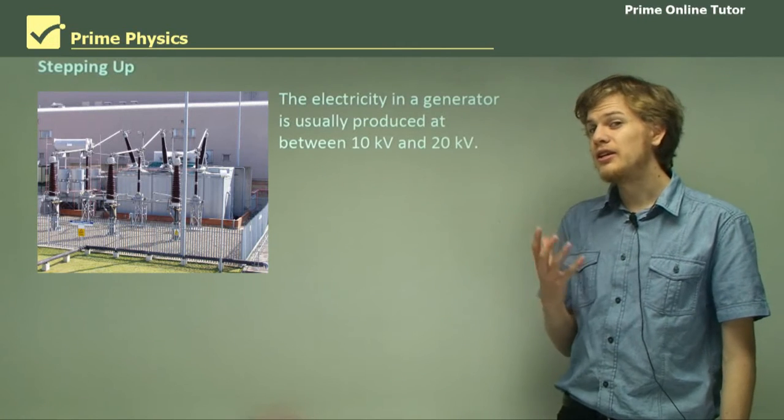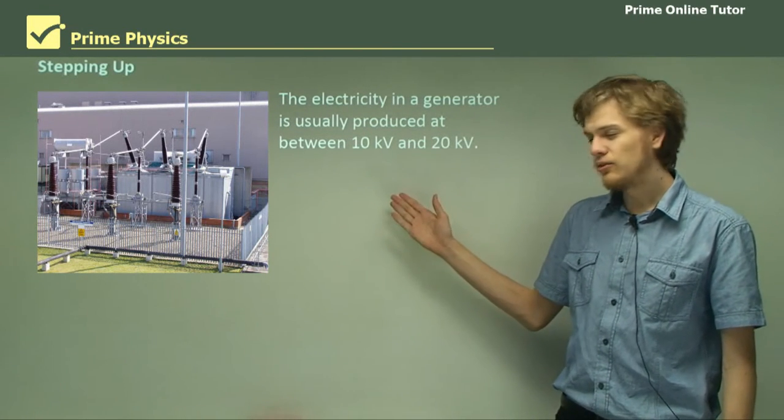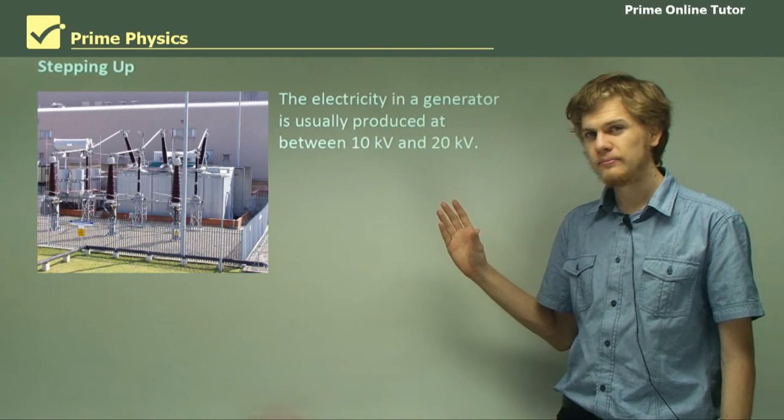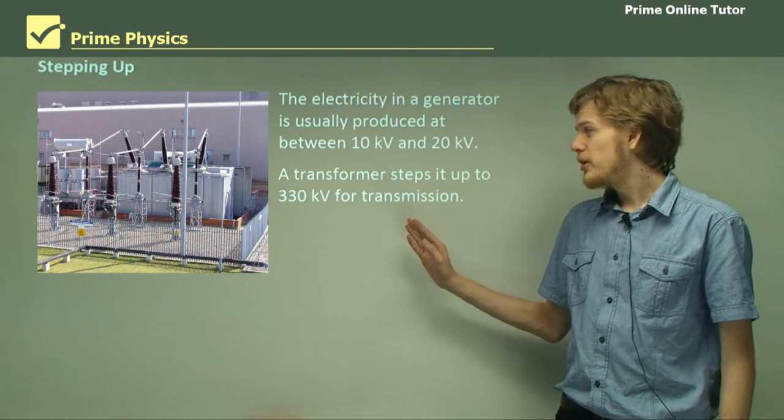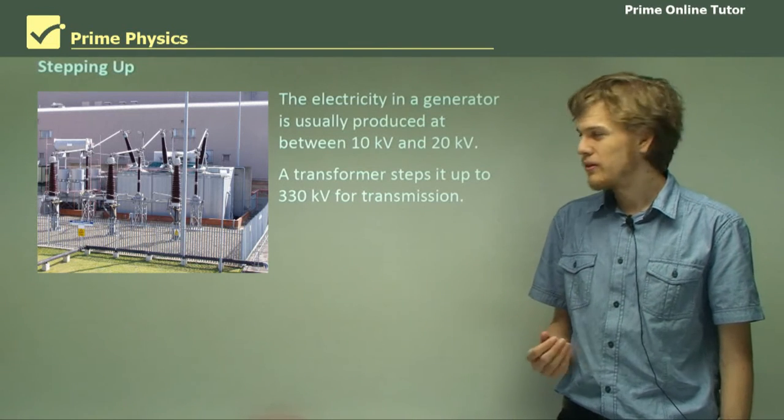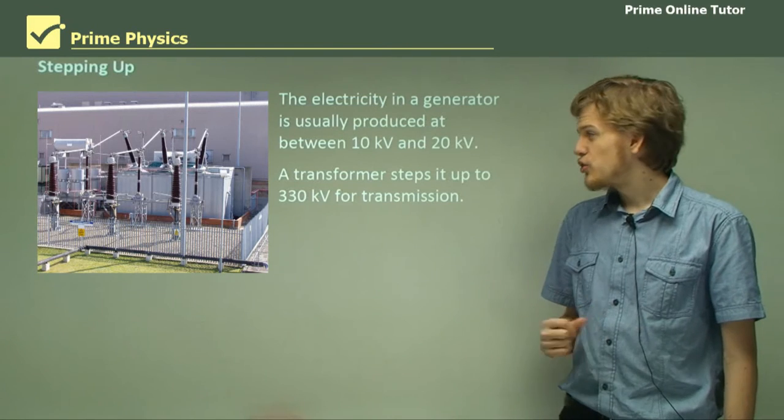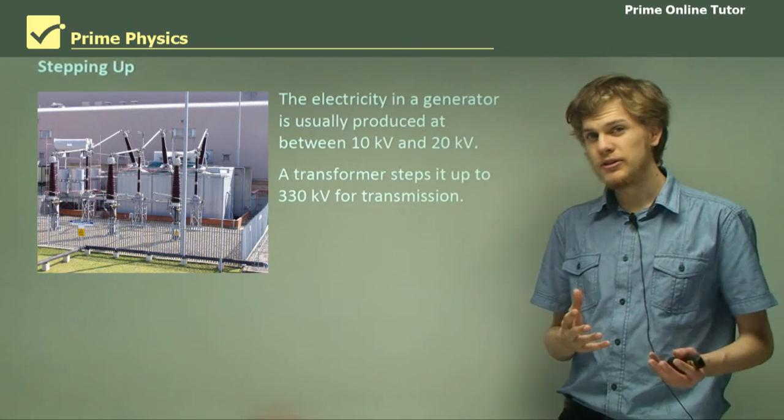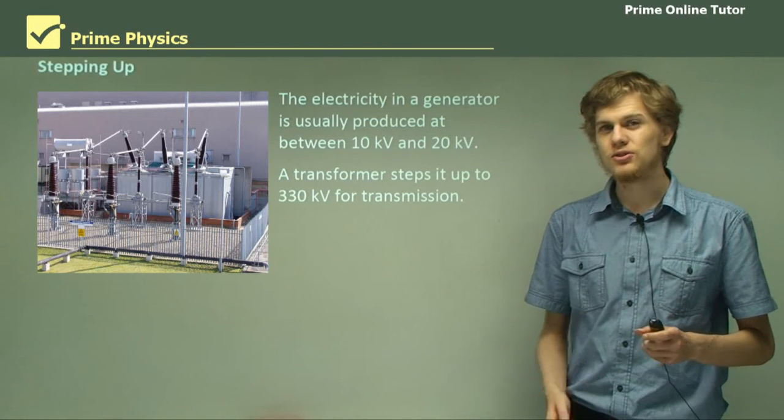Now the electricity in a generator is usually generated in the neighborhood of between 10 kilovolts and 20 kilovolts. A transformer will step this up to 330 kilovolts, that is 330,000 volts before it's transmitted long distance. This huge increase in voltage greatly decreases the current and therefore the energy lost as it's transmitted.